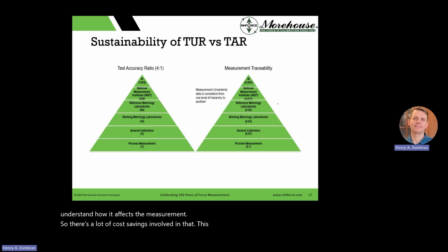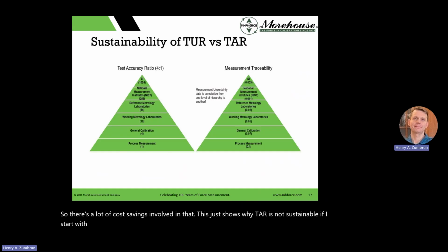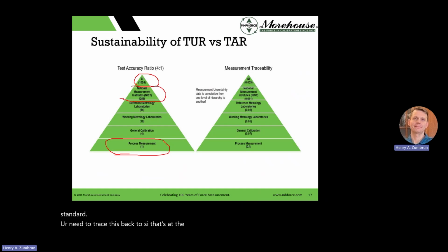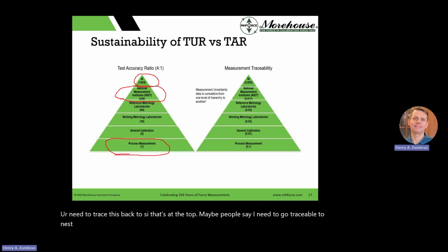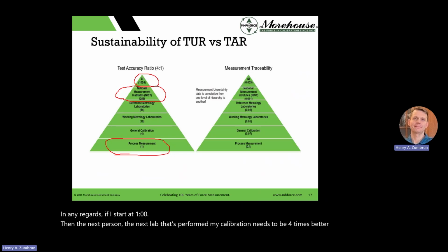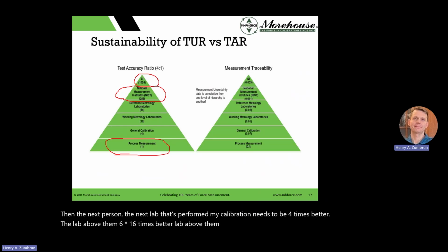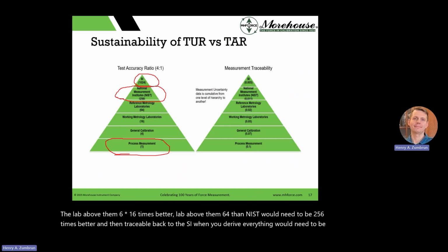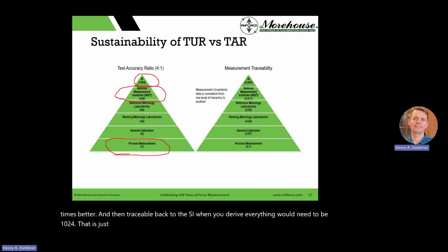This just shows why TAR is not sustainable. If I start with a process measurement down here and I need to go up to the national standard, or trace this back to SI, that's at the top. Maybe people say I need to go traceable to NIST. Nothing's traceable to NIST. It's traceable to SI through an NMI under the mutual recognition arrangement. In any regard, if I start at one, then the next lab that's performing my calibration needs to be 4 times better. The lab above them, 16 times better. The lab above them, 64. Then NIST would need to be 256 times better. And then traceable back to the SI, when you derive everything, would need to be 1024. That is just not sustainable whatsoever as far as 4-to-1 ratios.